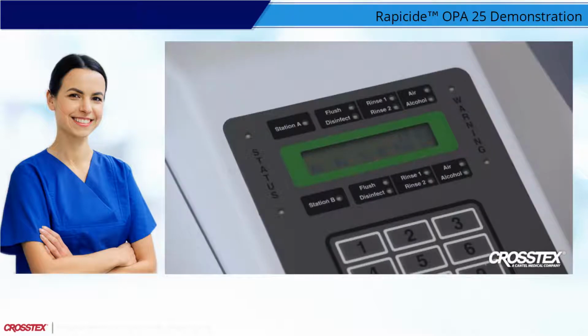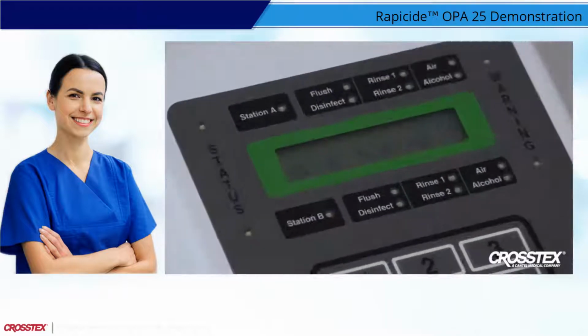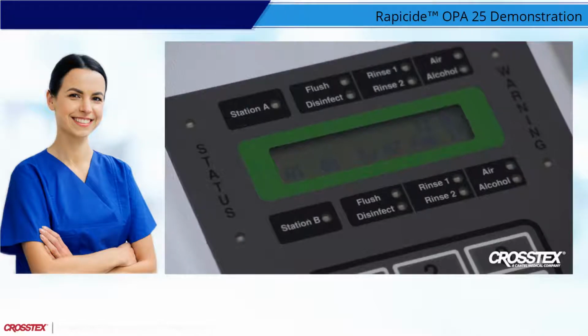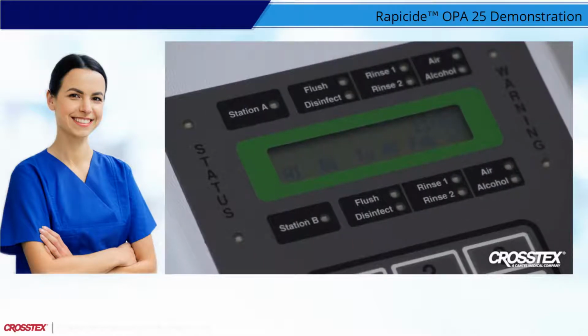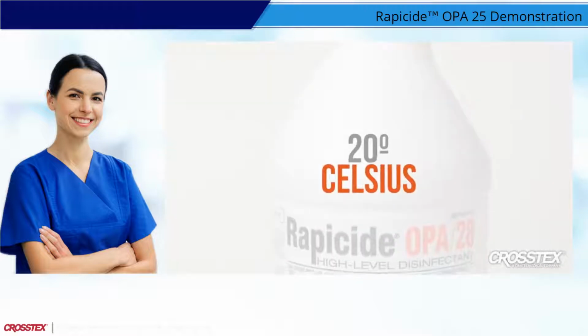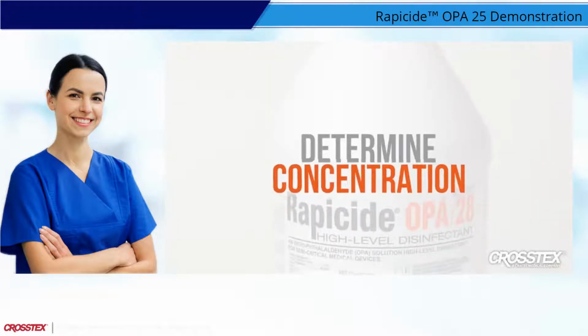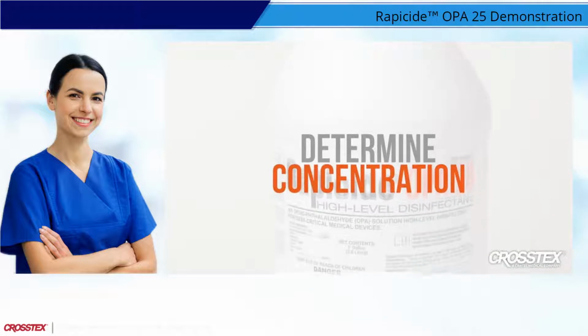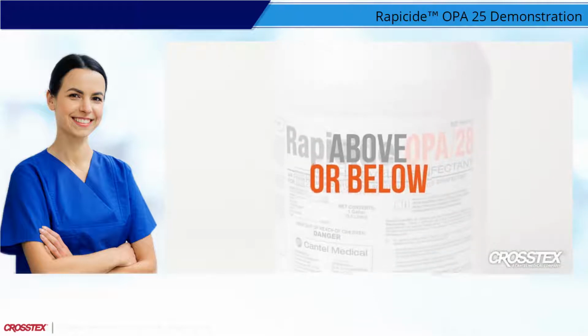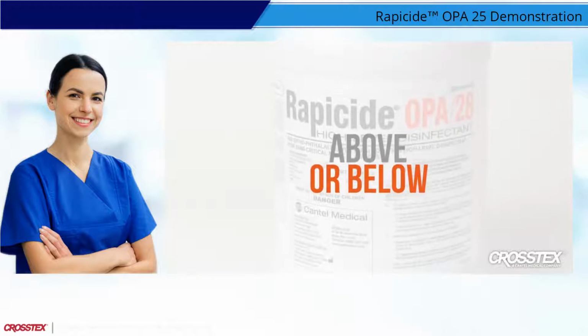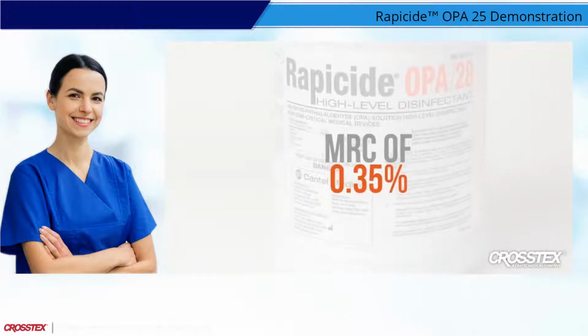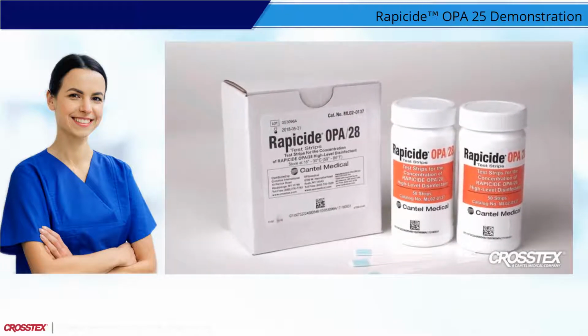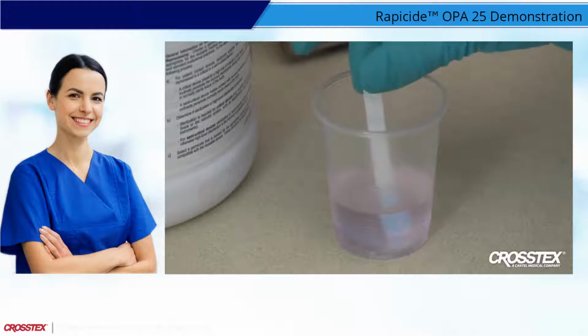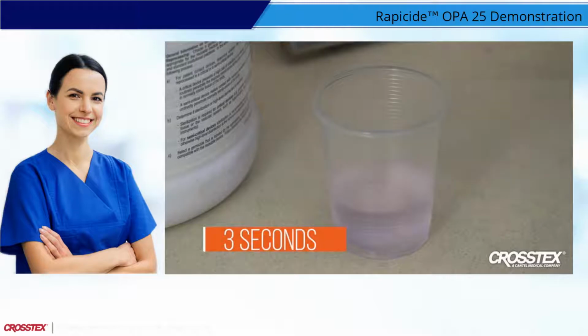High-level disinfection requires appropriate temperature, contact time, and length of use following solution activation. Always confirm the temperature of the solution in the holding tank is at least 20 degrees Celsius. Next, determine whether the concentration of OPA, the active ingredient in Rapicide OPA28 solution, is above or below the established minimum recommended concentration, or MRC, of 0.35% by using Rapicide OPA28 test strips. Immerse the entire indicator pad on the test strip into the Rapicide OPA28 solution for a full 3 seconds.